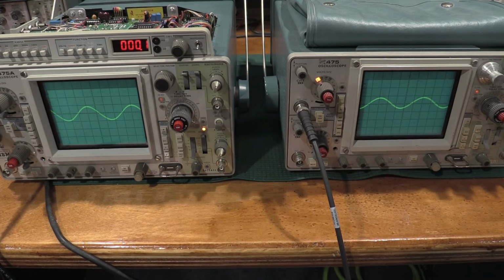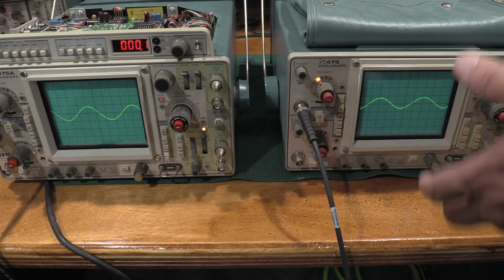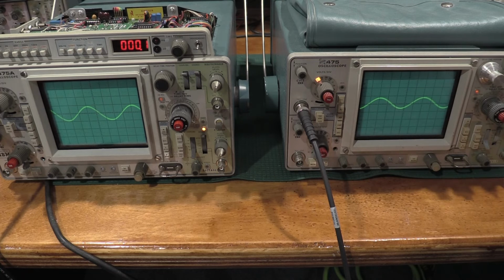Now, as I speed up the frequency, the amplitude is going to decrease just due to the limited bandwidth of the vertical amplifier. Some slight adjustments on the trigger to get a stable trigger would not necessarily be a fail. Not being able to acquire a stable trigger would be a fail. So depending on our trigger point, as the amplitude falls, we may fall out of trigger, in which case I might be able to bring it back. But that's what we're going to test. So we're going to step it up by 50.